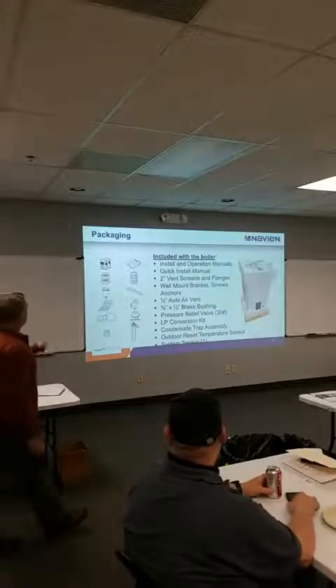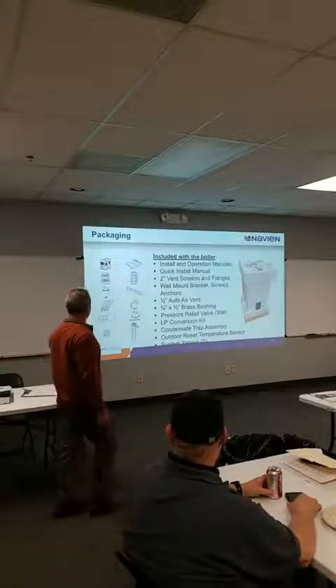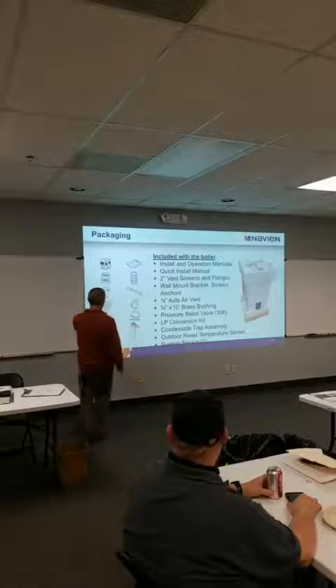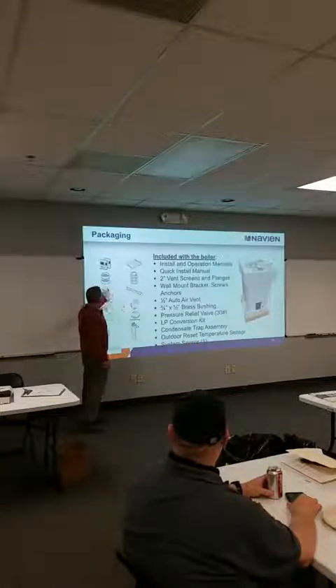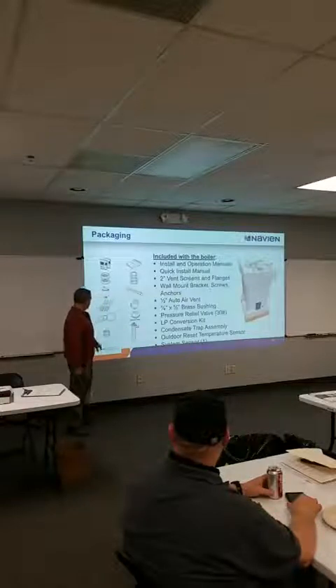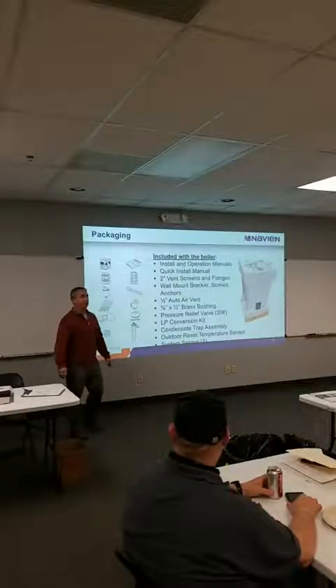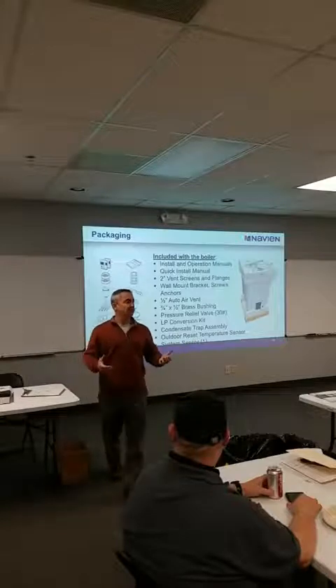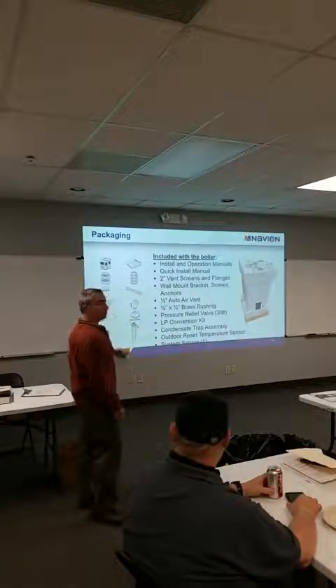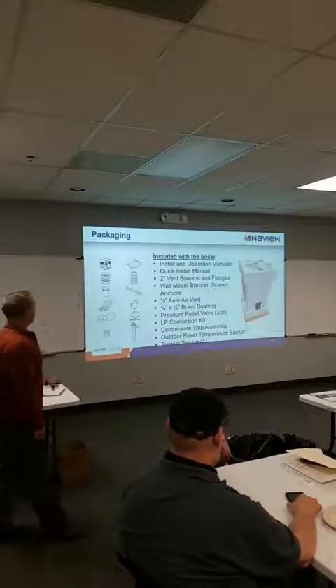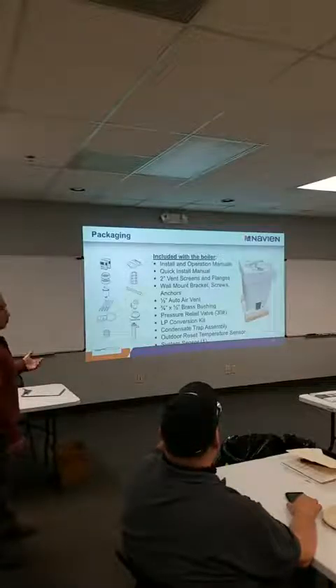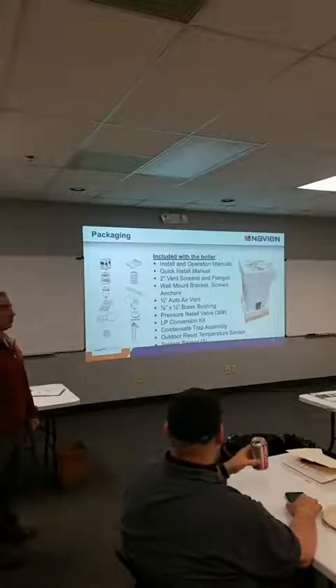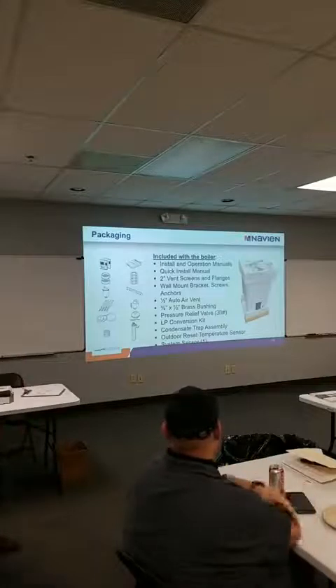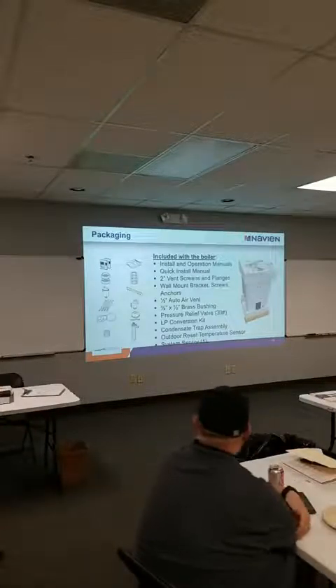So, this is what comes in this box. You're getting your outdoor sensor with it, your relief valve, a small little air eliminator, a condensate trap, and a little fitting to mount your air eliminator on top. You can also put a T up there, and put the relief valve up there as well if you want, and your air eliminator, and or an external low water cutoff if you want to put that up there as well, if you have to. There's an internal low water cutoff.